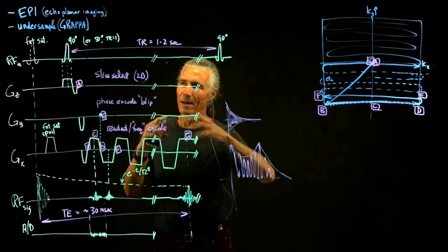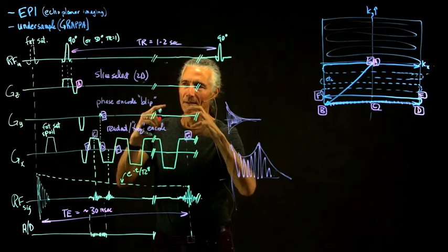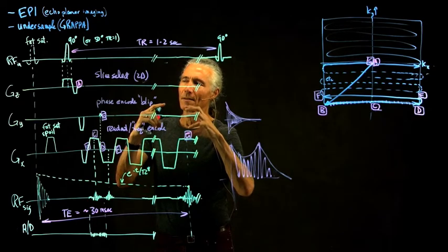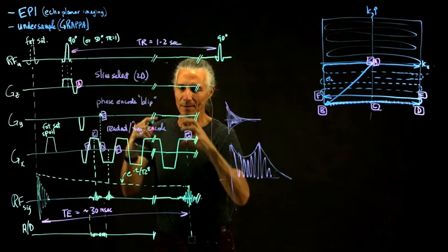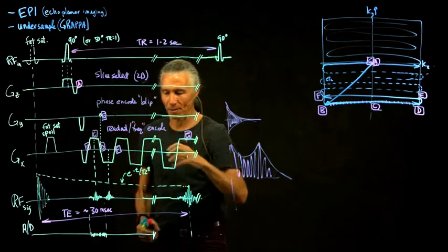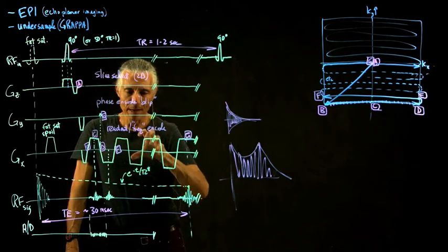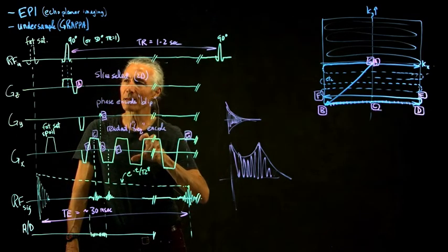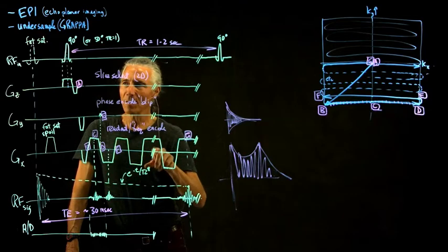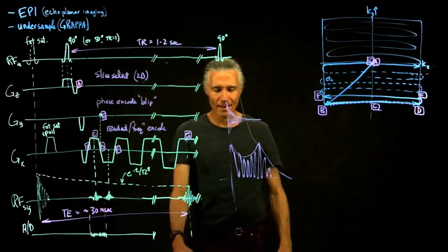They try to balance the torque, but basically when you power up the gradient coil, it's going to ever so slightly move. And then when you power it up the other way, it's going to try to move the other way. And so the gradient coil will wiggle back and forth. That's actually what the noise coming out of the magnet is. It's the gradient coil ever so slightly wiggling back and forth as you run these 1,000,000 watt pulses through it. So that's echoplanar imaging.